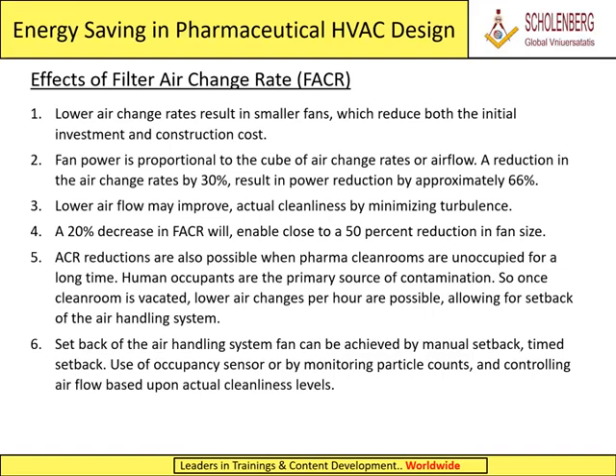5. ACR reductions are also possible when pharma cleanrooms are unoccupied for a long time. Human occupants are the primary source of contamination. So once the cleanroom is vacated, lower air changes per hour are possible, allowing for setback of the air handling system. 6. Setback of the air handling system fan can be achieved by manual setback, timed setback, use of occupancy sensors, or by monitoring particle counts and controlling airflow based upon actual cleanliness levels.